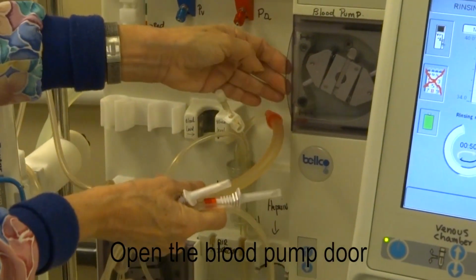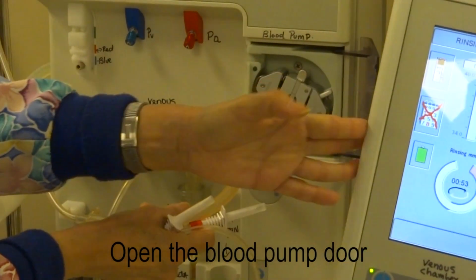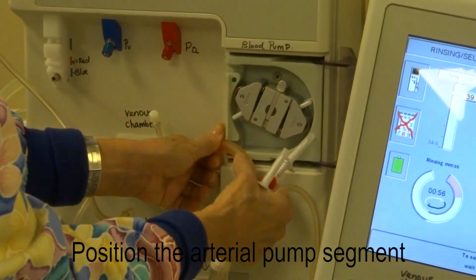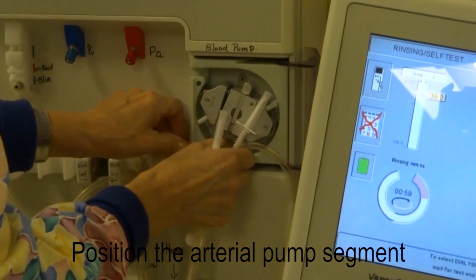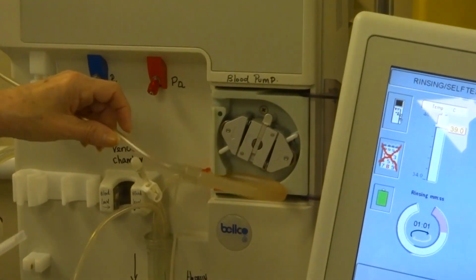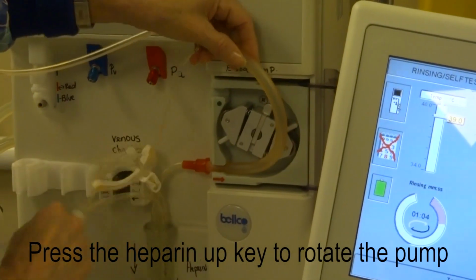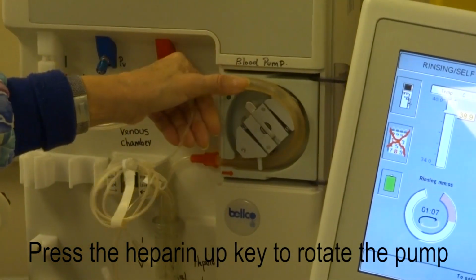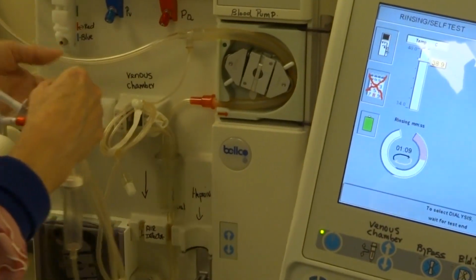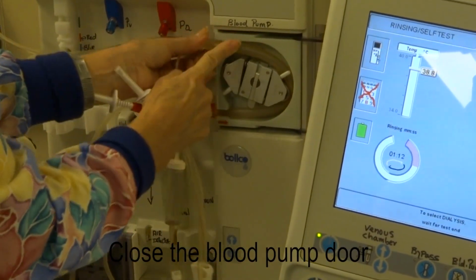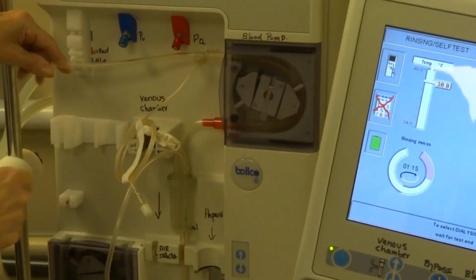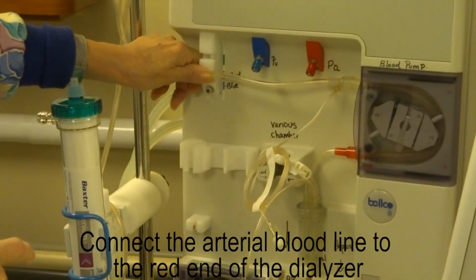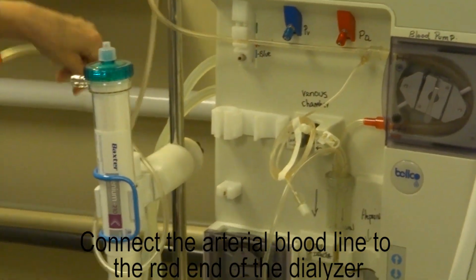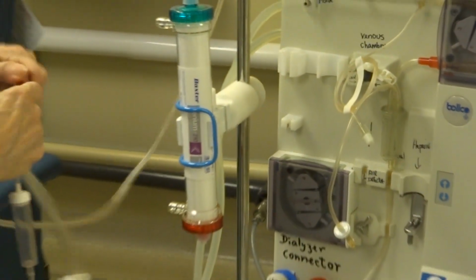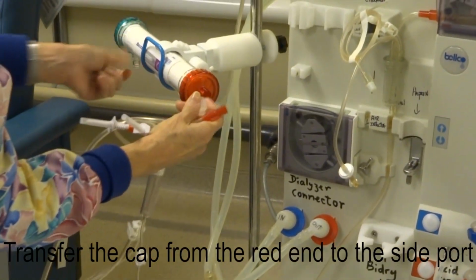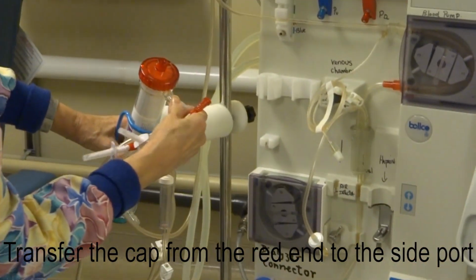Open the blood pump cover. Position the arterial pump segment in the lower guide set above the red arrow. Press the heparin arrow up key to rotate the pump until the arterial pump segment is inserted. Close the pump cover. Connect the arterial blood line to the red end of the dialyzer. Transfer the cap from the red end to the side port of the dialyzer.